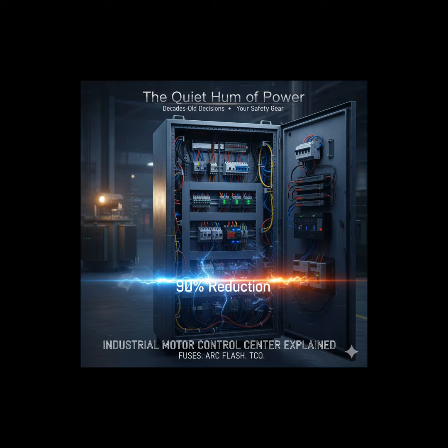Now we're moving to branch circuit protection, and we have to clearly distinguish between an overload and a short circuit. Two different animals. Totally different. An overload is excessive current that builds heat slowly. A short circuit is instantaneous and catastrophic. Two conductors touch, resistance drops to near zero, and the current instantly skyrockets. We're talking thousands or tens of thousands of amps.